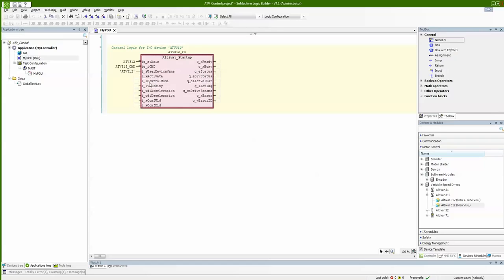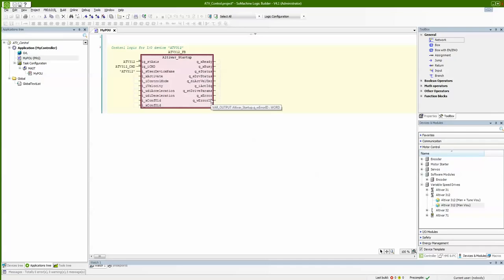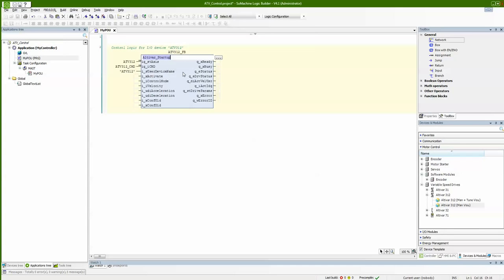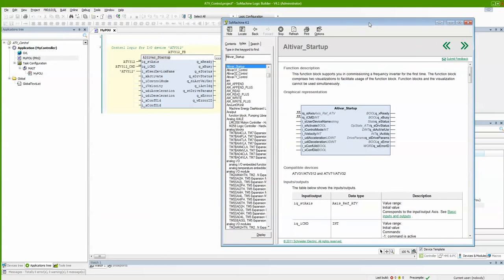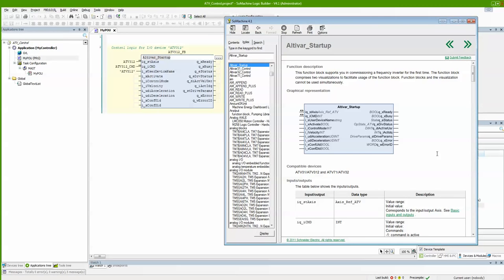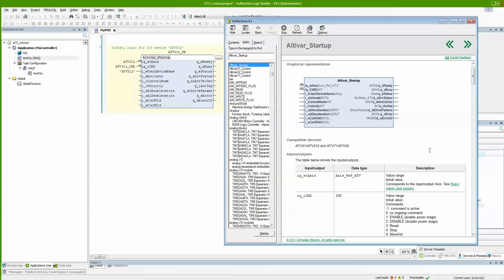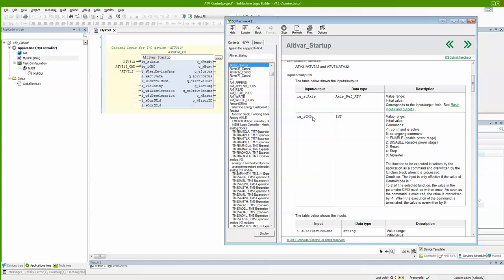The function block has a command word to provide control of the axis, and a control mode to define where control comes from — from the application or from visualization. I have velocity, ramp reference, and output. Status values, actual velocity, and current consumption of the drive are also available. I can click F1 while standing on the function block and it automatically opens the help file. From the help file I can read: command word 1 enables the drive, 2 disables it, 3 resets, 4 stops, and 9 moves at velocity.